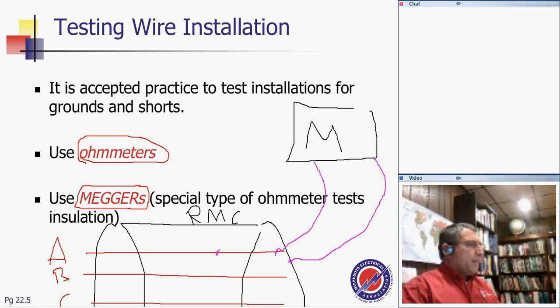Then you have the same lead, and go to phase B, and then move it to phase C, and the same lead move it back to the neutral. So that will get you the insulation, in this case between phase A and the conduit, phase A and phase B, phase A and phase C, and phase A and the neutral. So if you measure a very high impedance, this means insulation is in good shape.